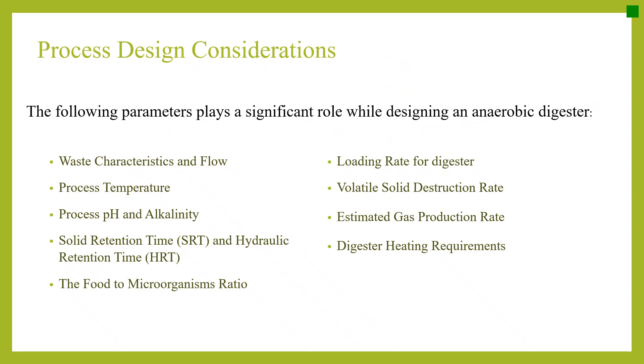The following parameters play a significant role while designing an anaerobic digester: waste characteristics and flow, process temperature, process pH and alkalinity, solid retention time, hydraulic retention time, the food to microorganism ratio, loading rate for digester, volatile solid destruction rate, estimated gas production rate, and digester heating requirements. Some of these parameters we have already discussed earlier, but here we are going to discuss them all over again because they all play a very significant role while designing an anaerobic digestion process.